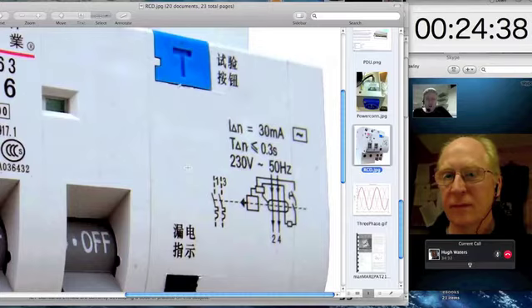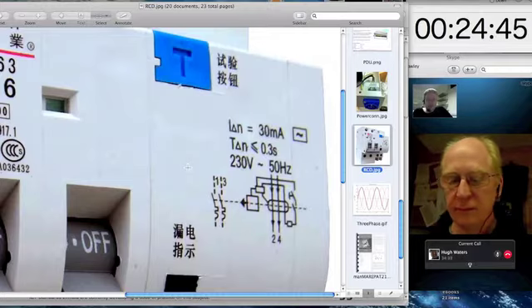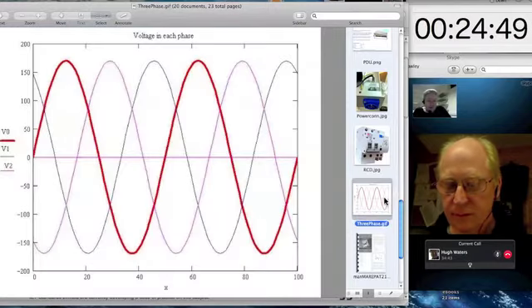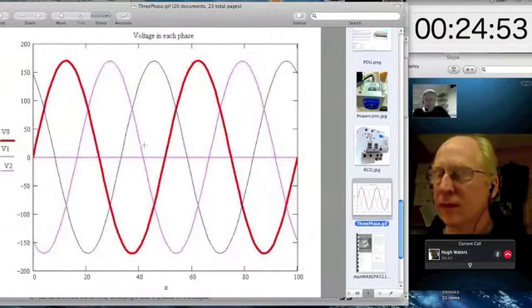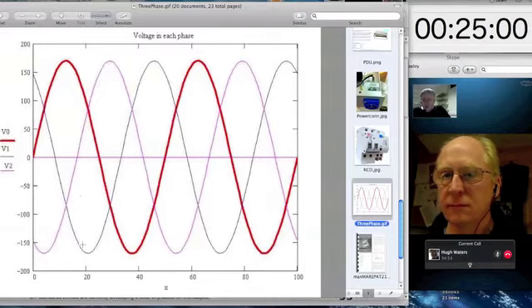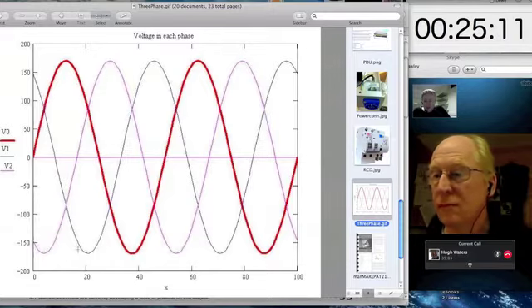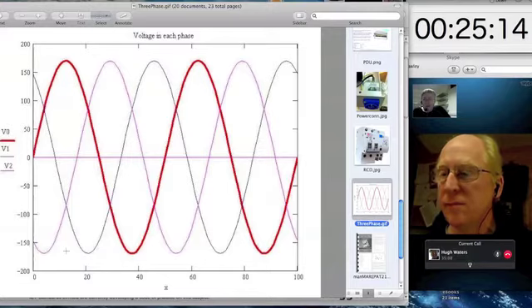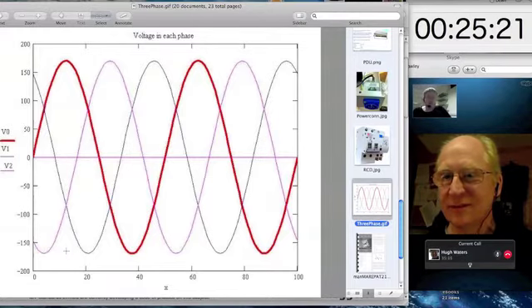And it's the introduction of reliable RCDs that really allowed for things like mixed phases within machine rooms and things like that, because they essentially provide an awful lot of protection. Because think about it, I'll go back to our 3 sine waves showing what's coming out of our generator and hence what's coming into our mains intake in our facility. There are times where the difference between one phase and another phase is an awful lot more than just 240 volts. You've got more than 400 volts between that negative going dip there and that positive going spike there. And that's why 3 phases are dangerous. I mean, mains is dangerous, but 3 phases are doubly so, because you can get across huge great voltage differences, not just the difference between neutral and live, which is 240 volts. You can get very much larger shocks.